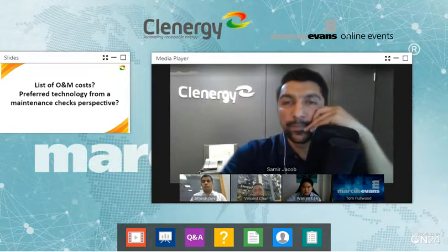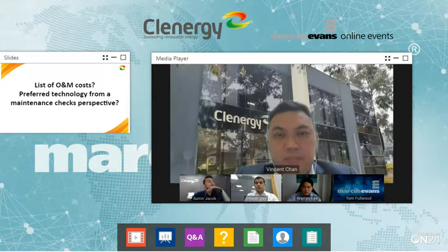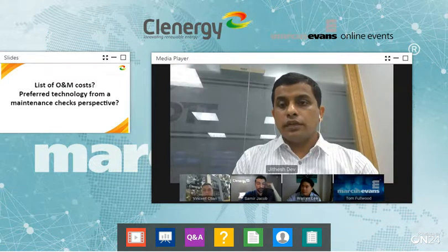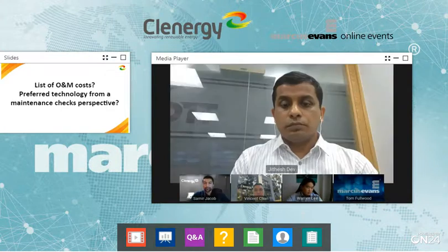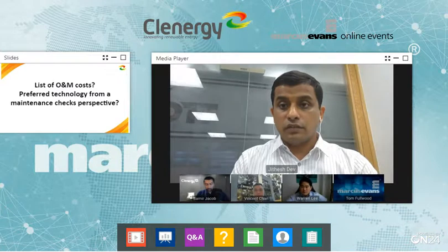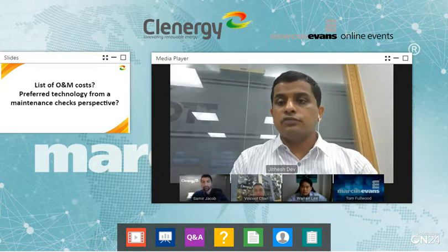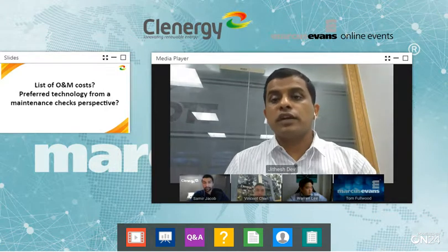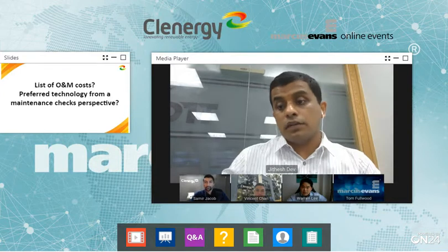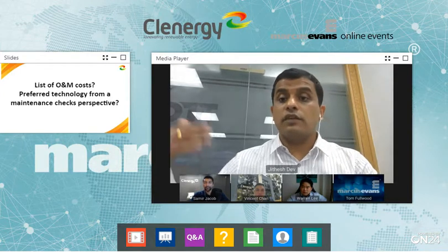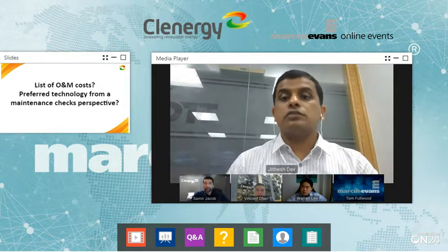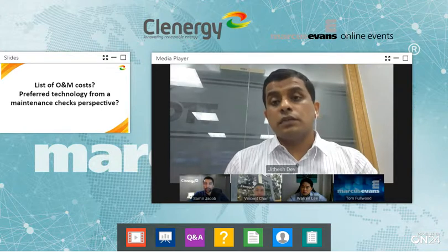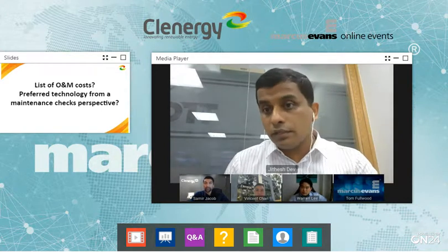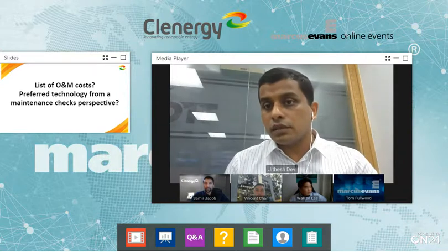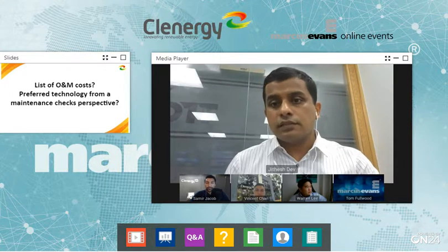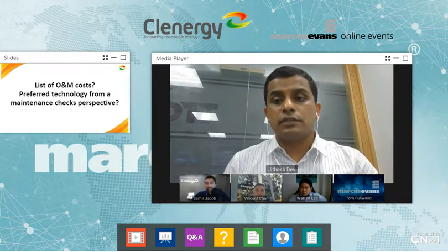You can have an O&M plan for the first 2 years based on your plant performance and the failures happening. You can do an MTTF or MTBF analysis, then improvise your preventive and corrective maintenance plan. Thereby, the plant maintenance can be improved over the next 5 years. So every 2 years or every 5 years, you need to do this evaluation and improve preventive or corrective maintenance. In addition, training of technicians and engineers is a key parameter.